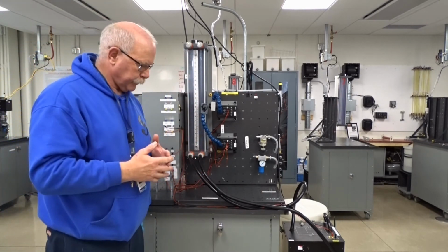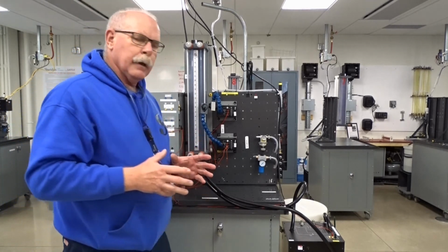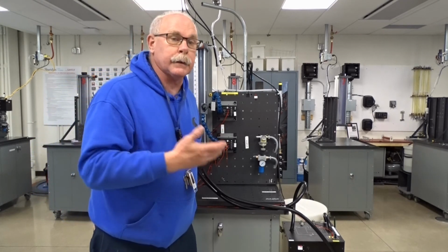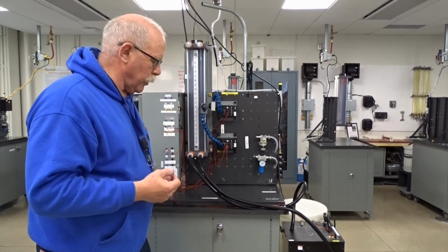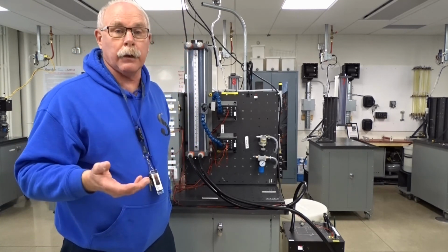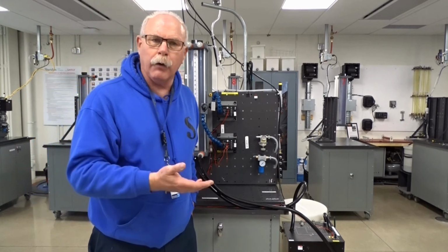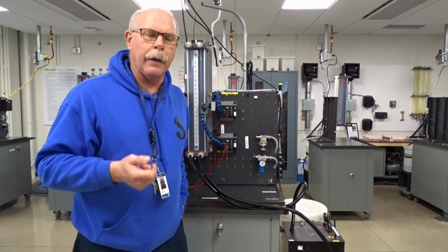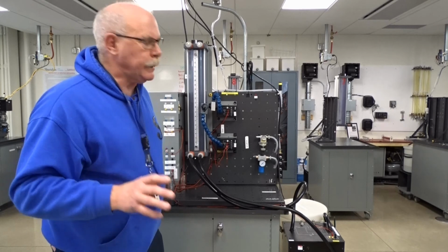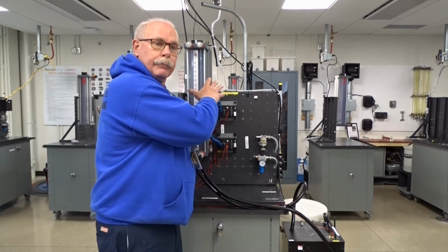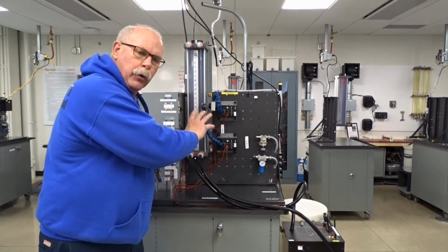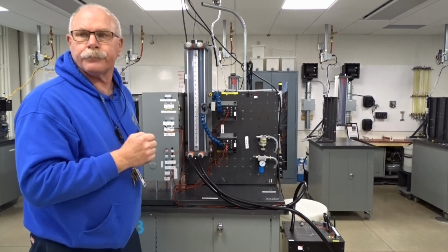What you hear now, because I've reduced that dead band, is this pump cycling on and off. For a small motor like this, that isn't a problem. But if this happened to be a larger motor, having it turn on and off, that inrush to the motor could cause a lot of wear and tear. Also, if this was a valve, the valve would be cycling open and closed a lot. So having that dead band in there actually saves the equipment. And we don't need to have it at exactly any point. We're just worried that it's going to be between two points of our range.